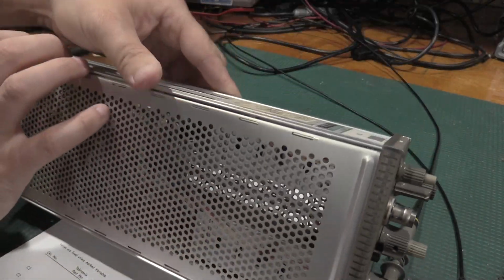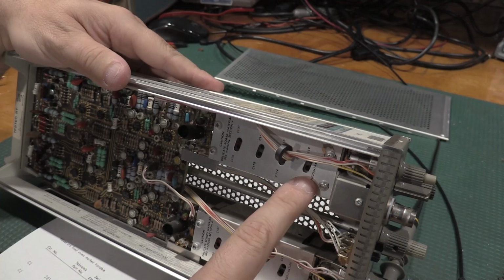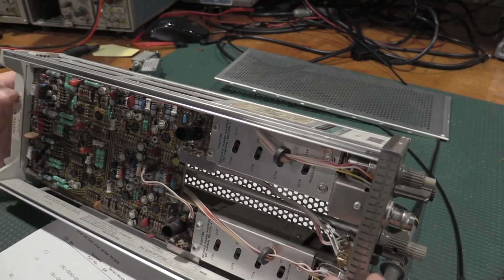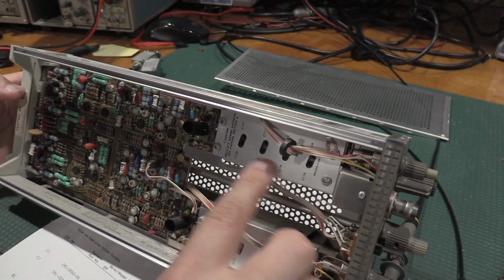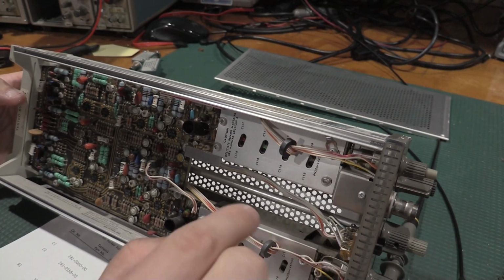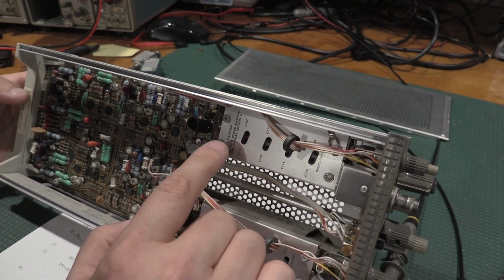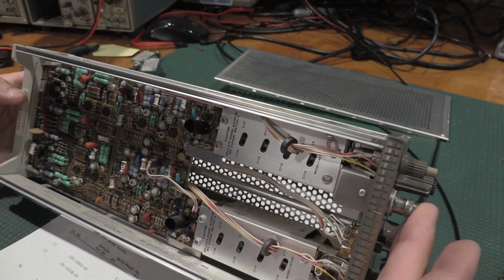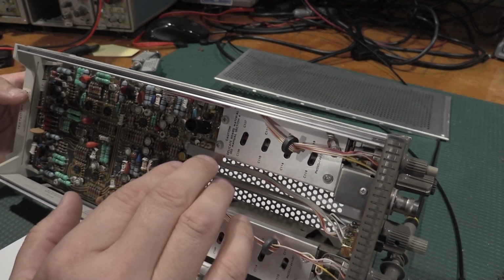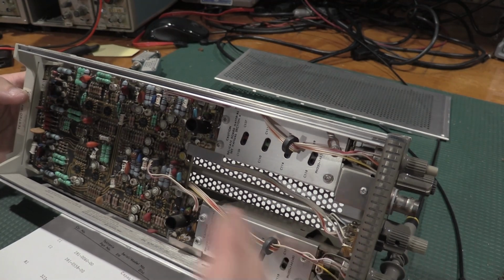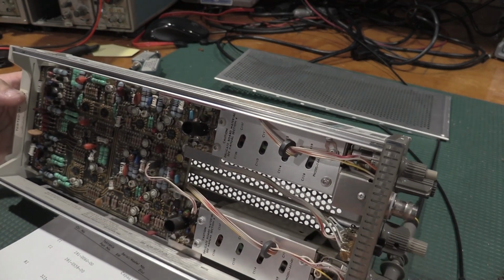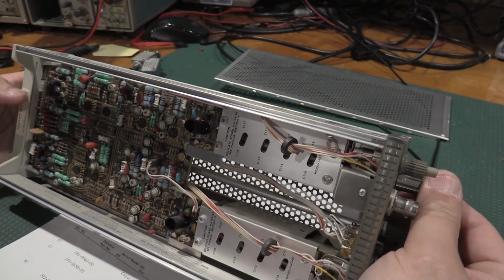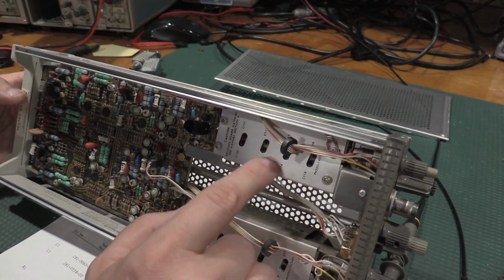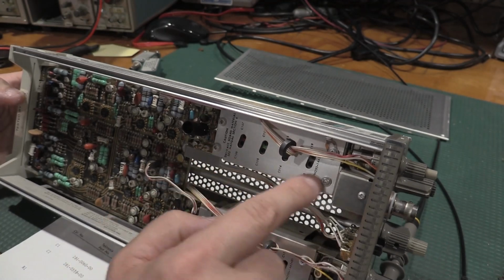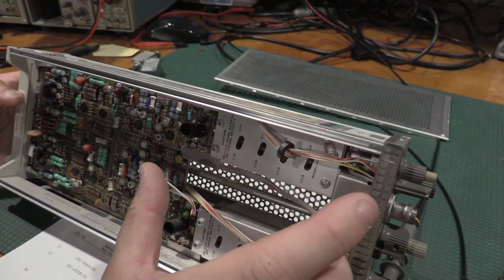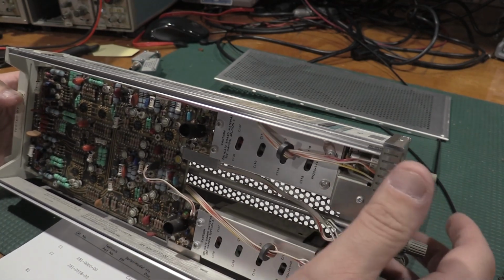Because once we set the capacitance at the front end, we want to normalize this capacitance so it's all the same. Because if you don't, you'll have to reset the probe every time you change ranges, and that's what we don't want to do. So once it's set up and the square waves are flat, all of these attenuators match that input capacitance. That way, once you set the probe once, any range you set the probe in is good for the whole channel, so you don't have to readjust every time you change ranges on the front, which you would have to do if these were out of whack. And they can get really far out of whack. These 8 capacitors specifically have a huge effect on the displayed signal on the scope.